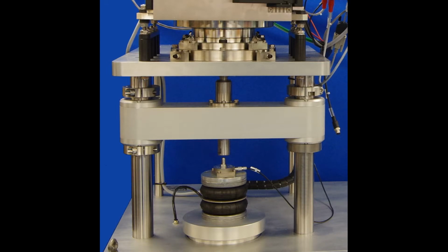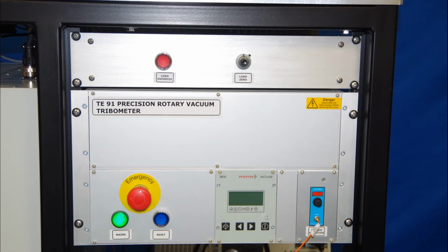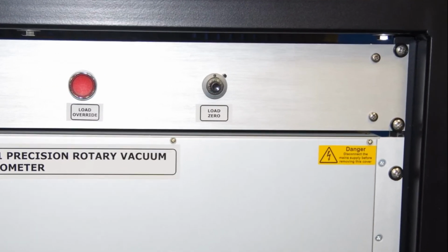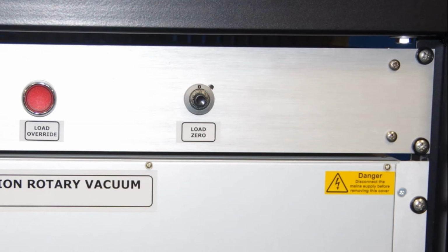The bottom of the loading shaft is connected to the machine crossbeam, which is loaded vertically by a servo-controlled pneumatic bellows. Column clamps have been fitted on the pillars to restrict the travel of the crossbeam. This is to prevent damage to the stainless steel bellows. A force transducer fitted to the pneumatic bellows measures the load and provides feedback for control. The force transducer is connected to a signal box under the machine with a potentiometer to zero the load.